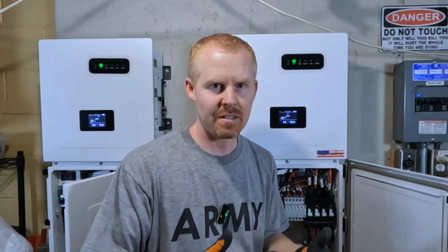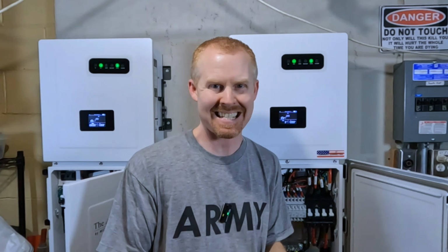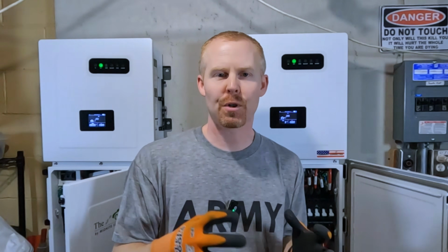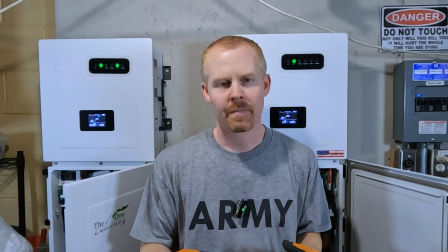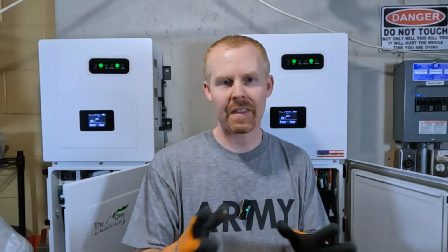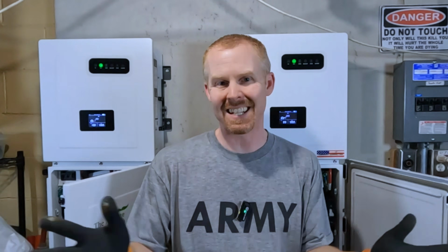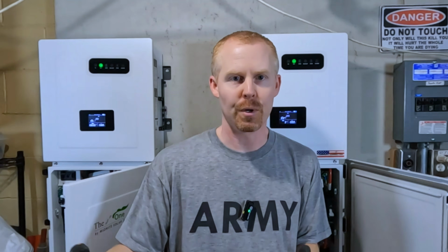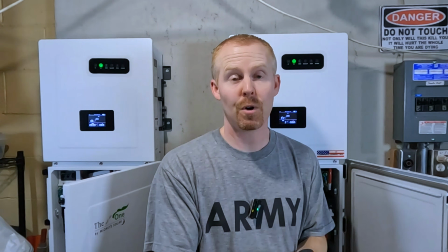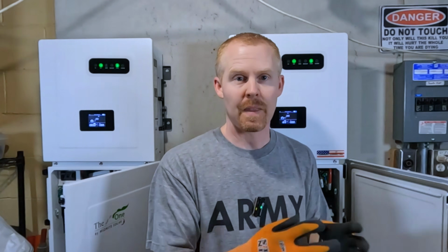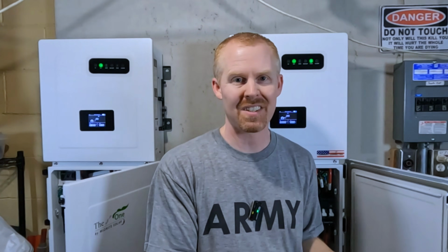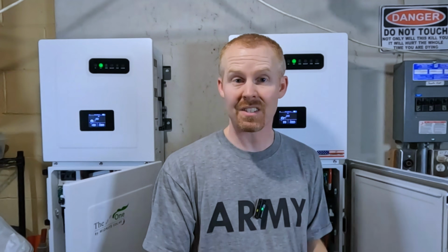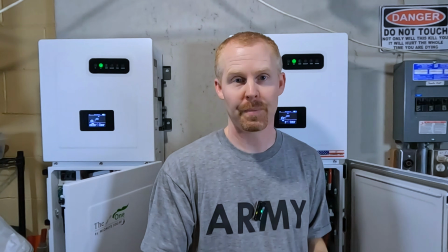And then while we're waiting for these to get to their standby state, the way the Midnite inverters decide which one is going to be the master is based on which one is going to have BMS communication to the batteries. That's assuming you're using a shared battery bank and not a split battery bank, one for each inverter. And if you're using a self-consumption mode or a sellback mode, that master inverter that has the BMS communication also needs to have the CTs connected to it. You only need the CTs connected to the master inverter.